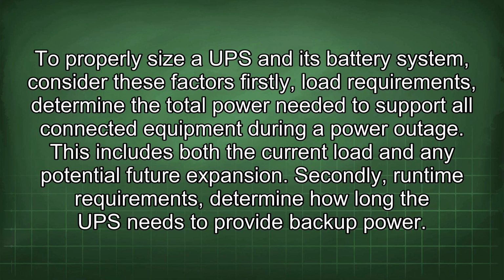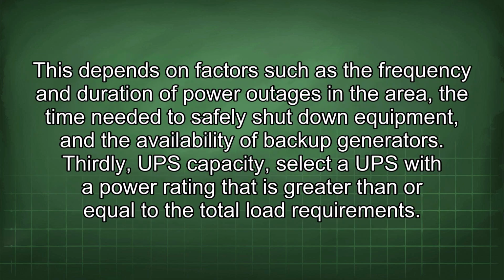To properly size a UPS and its battery system, consider these factors. Firstly, load requirements. Determine the total power needed to support all connected equipment during a power outage. This includes both the current load and any potential future expansion. Secondly, runtime requirements. Determine how long the UPS needs to provide backup power. This depends on factors such as the frequency and duration of power outages in the area, the time needed to safely shut down equipment, and the availability of backup generators.